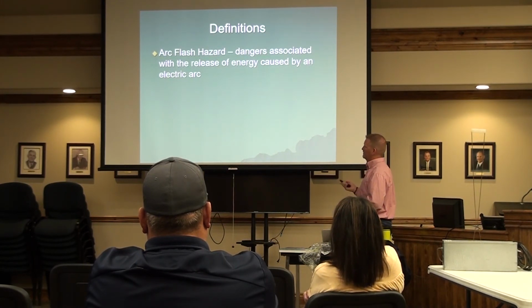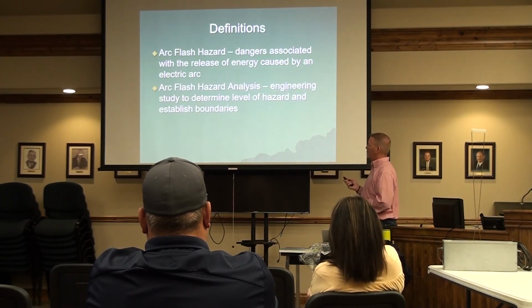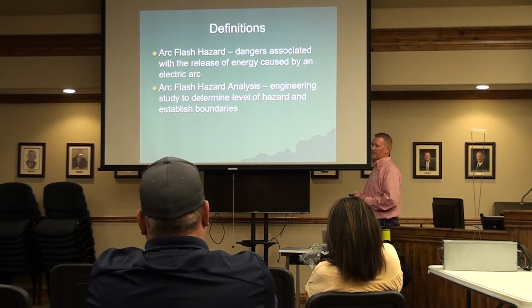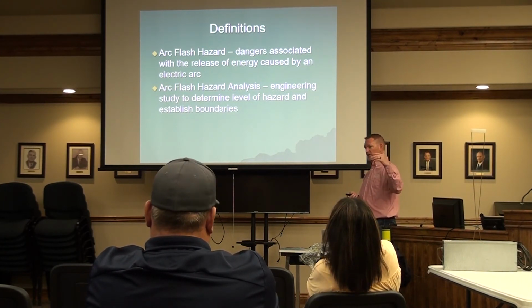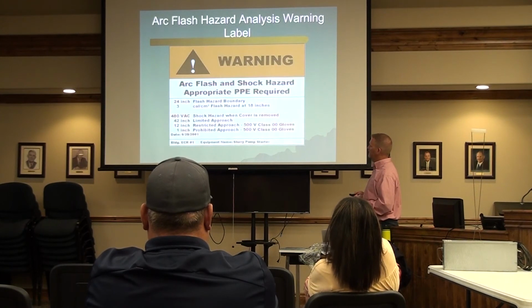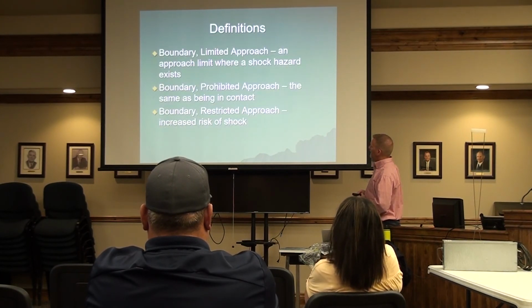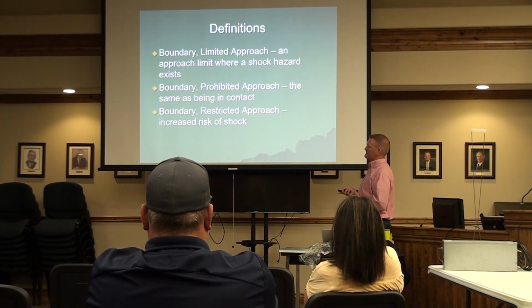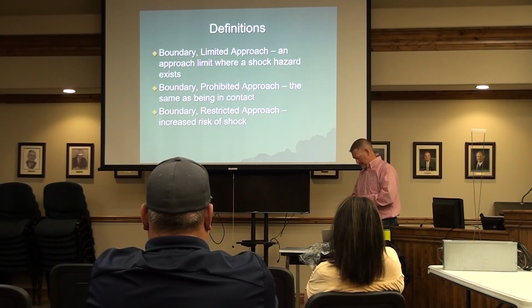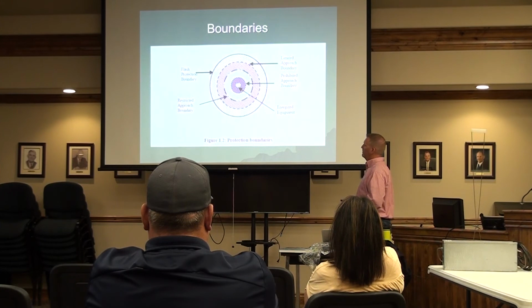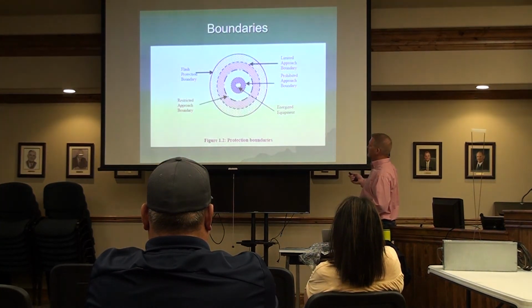So arc flash hazards, we've gone through that pretty well. Arc flash hazard analysis is where an electrical engineer does the analysis and puts the label on it - there it is again, and these are the boundaries. I don't want to get too deep into this since we're running close on time, but there are different boundaries for the different flash protection depending on how far out you are from the gear. Obviously, as you get further out, the lesser the hazard that exists.